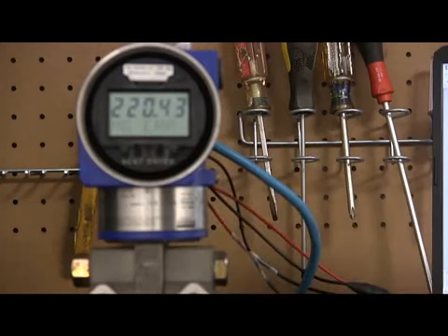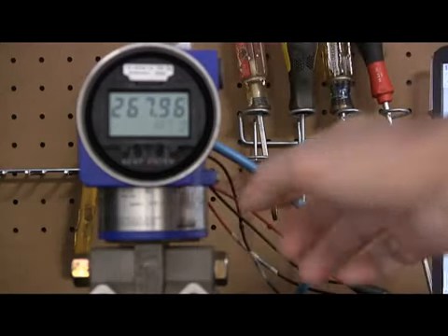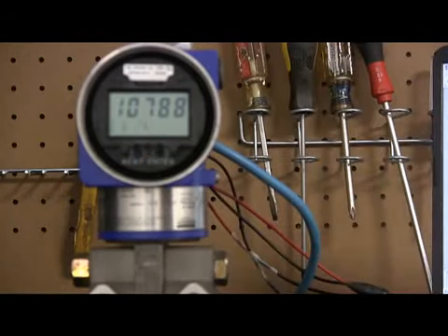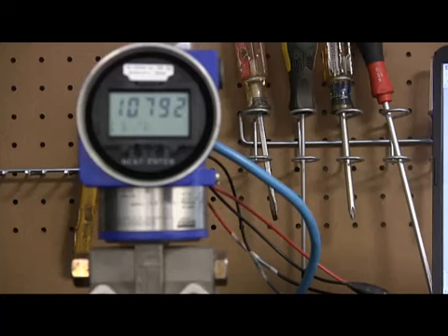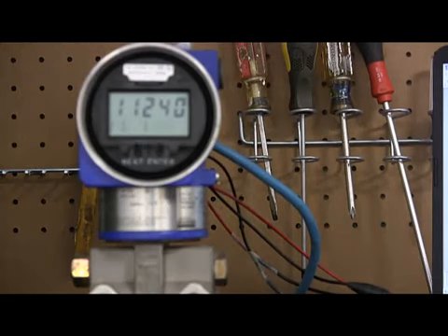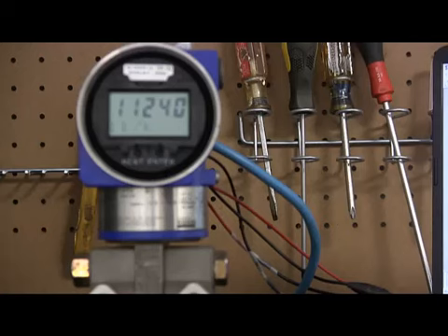So I'm going to go to the temperature measurement. We'll see it's 220. So I'm going to click my decade box up to 268 degrees F, and now you'll see the M6 error no longer appears. If I go back to the flow rate, there's my flow measurement, no M6 error. However, if it goes back down to 220, the error reappears. Now, perhaps we need to run at temperatures lower than 220.